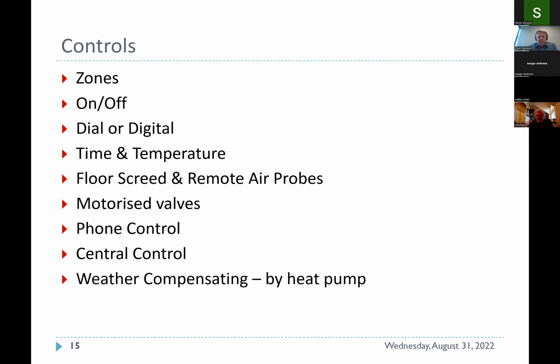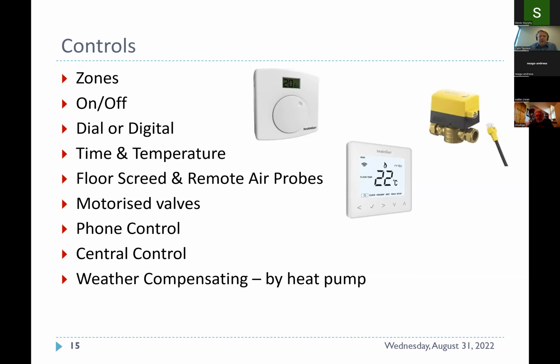Weather compensating is very important. Typically, this is very rarely used with boilers in domestic applications, but all heat pumps out there will have that built in as standard. Just an example of thermostats that are being used at this point, with a dial. It's very important to have a thermostat when you use particular heat pump installations to ensure that the end user can see the temperature.